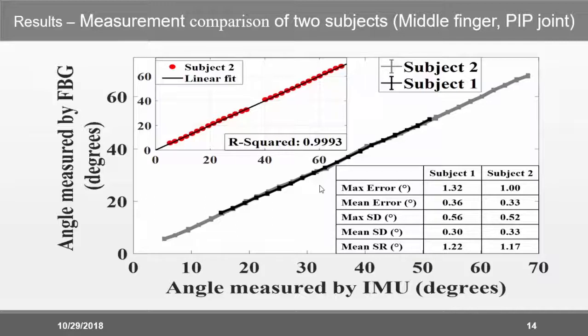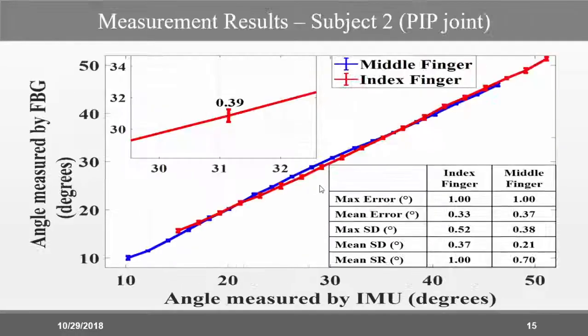We found very good agreement between both results. For subject 1 and subject 2, the maximum error for 5 repetitions of this experiment came out to be 1.32 degrees and 1 degree, while the maximum standard deviation was 0.56 and 0.52 degrees.